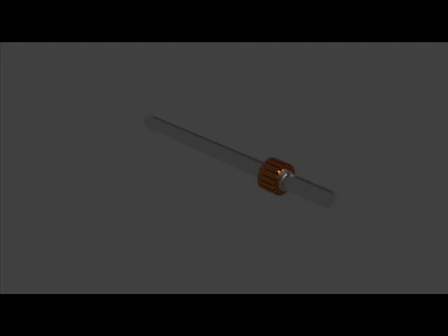It is essentially of cylindrical structure and is built up of high conductivity hard drawn copper or drop forged copper. These segments are insulated from each other by thin layer of mica. The segments are held together by means of two V-shaped rings that fit into the V-grooves cut into the segments.